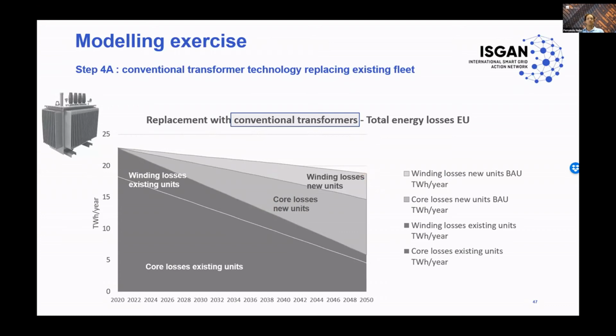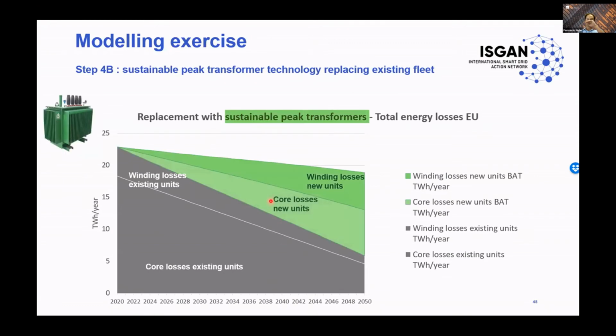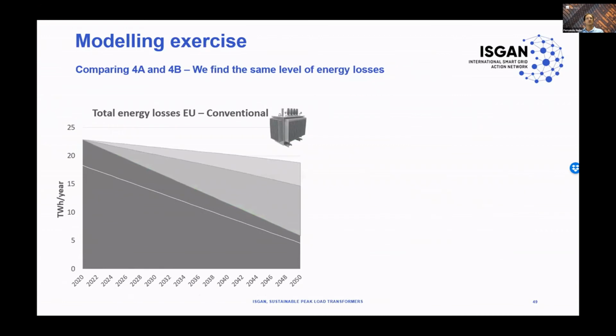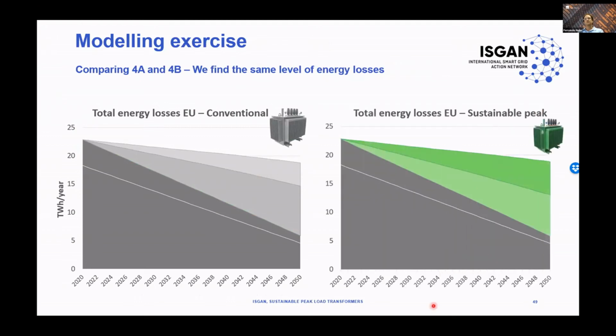But then let's see what happens if we replace these old transformers with sustainable peak transformers. Actually, the shape of the curve is quite the same. We have less core losses in exchange of more winding losses, but overall it's quite the same. Actually, let's see that in a combined slide. So we have the conventional units here in light gray, and then the sustainable peak units in green. So what we find is that actually the level of total losses remains the same. We have simply shifted more core losses for less core losses and a bit more winding losses.